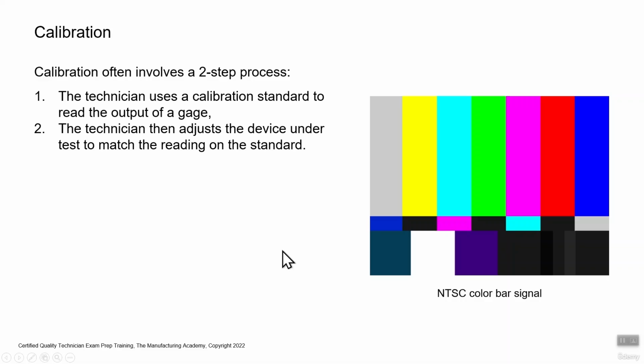So calibration often involves a two-step process. Number one, the technician uses a calibration standard to read the output of the gauge. And then, but not always, but often, the technician adjusts the device under test to match the reading on the standard. So calibration absolutely includes adjustments, if it's possible. And many different types of gauges have adjustments, hardness testers and calipers and micrometers and all sorts of test equipment has offsets and adjustments that you can make to tune it in closer to that true value. Not everything, of course. Gauge blocks, for instance, wouldn't have that.